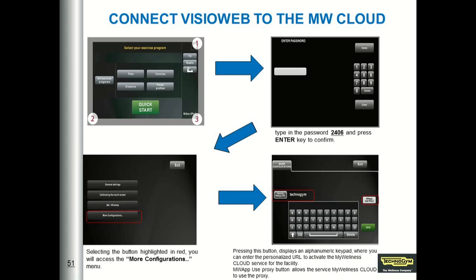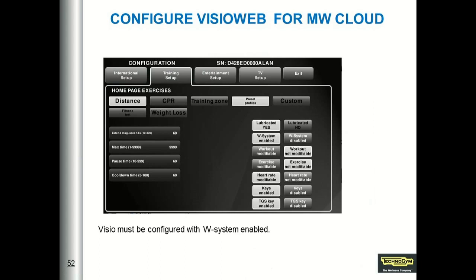To insert the facility URL in VisioWeb, this is also very similar to VisioSelf. You must touch the three corners in the sequence displayed in this slide, enter the password 2406, select 'More Configuration,' and write the facility URL. Note that when you have VisioWeb connected to MyWellnessCloud, the button WSystem must always be enabled.